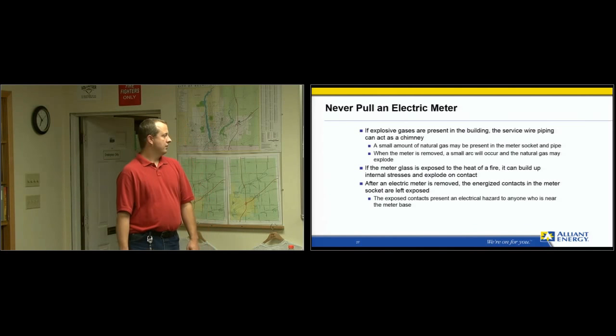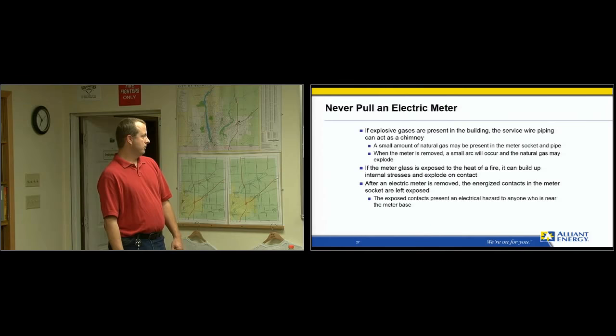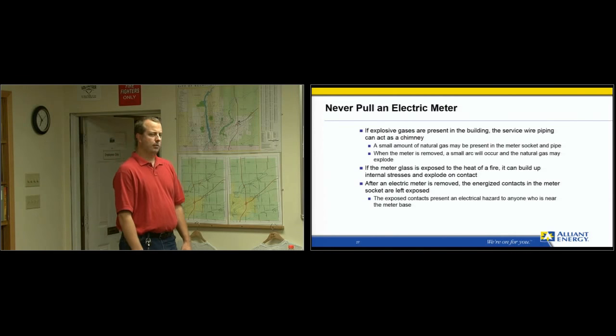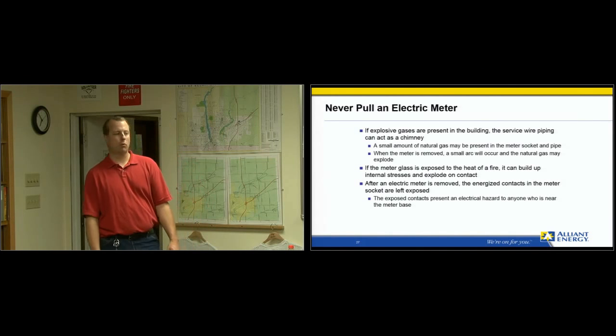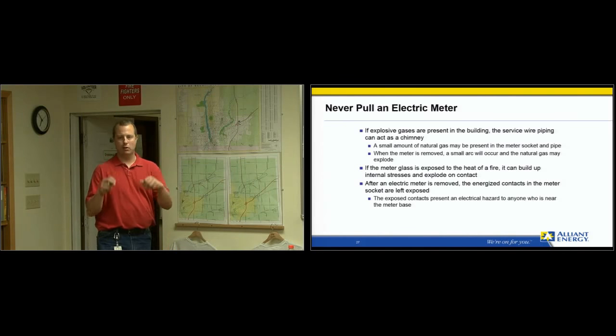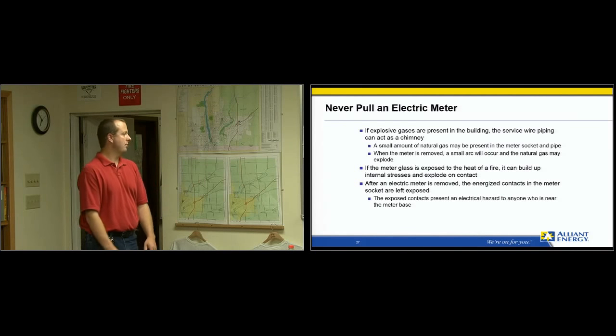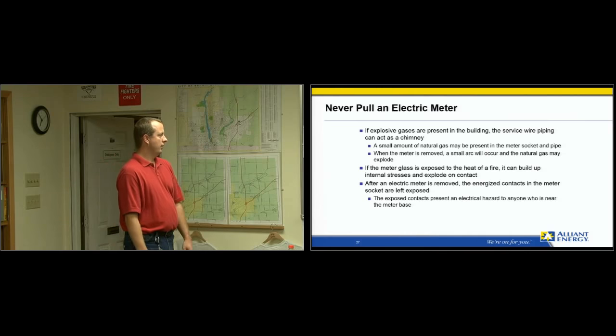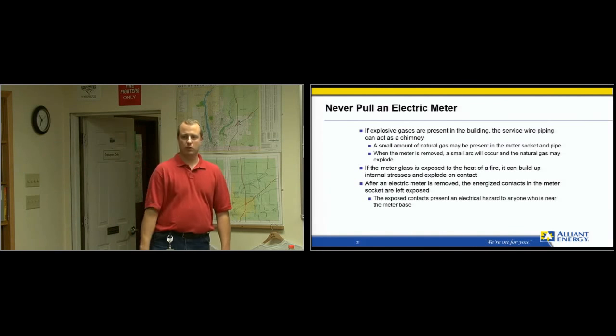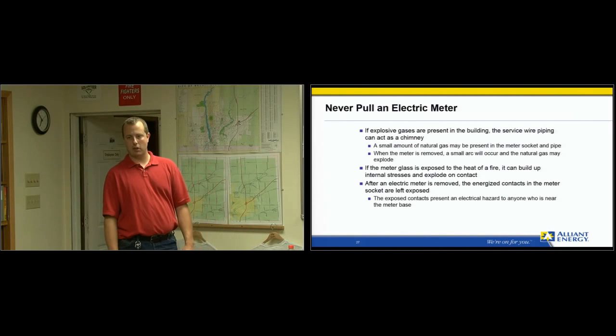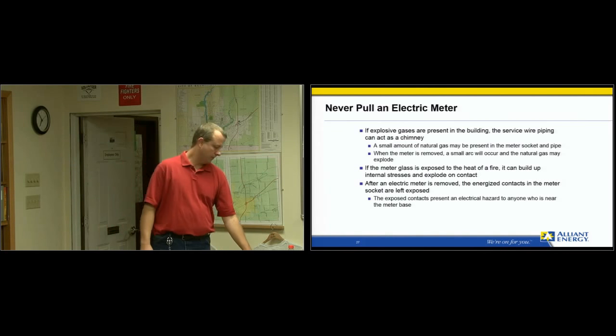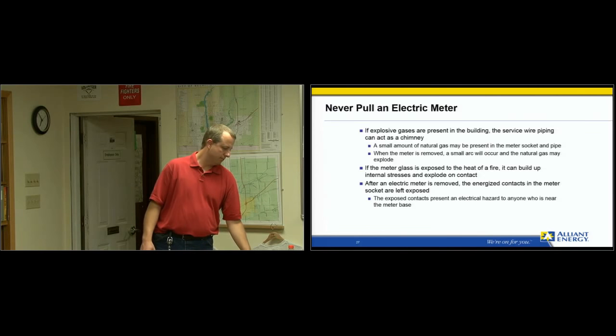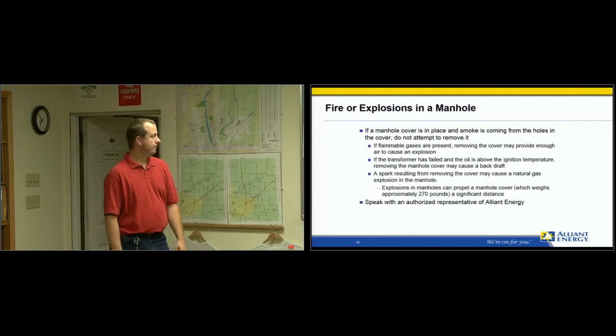Meter glass exposed to heat and fire can build up internal stress and explode on contact. A lot of our meters have gone to plastic now, kind of a throwaway or cheaper, or they have electronics in them, but they can still build up gases. The energized contacts in the meter are left exposed if you pull a meter, so you'll see a lot of our guys either cut it at the pole, or we've got a clear plastic plate we'll put on there if there's a chance we might re-energize or reset a meter.